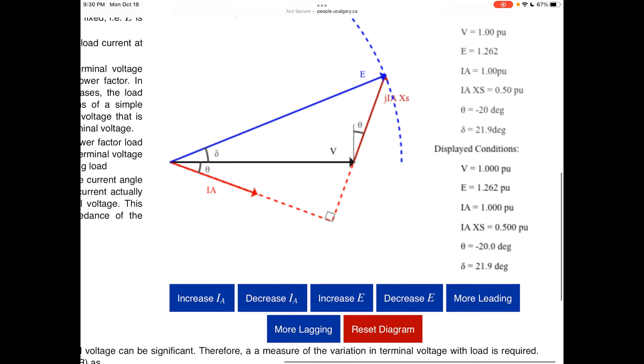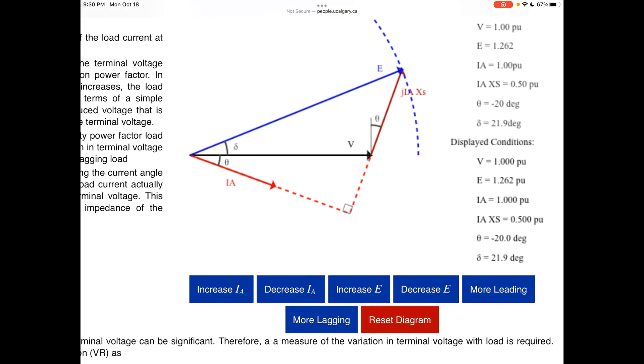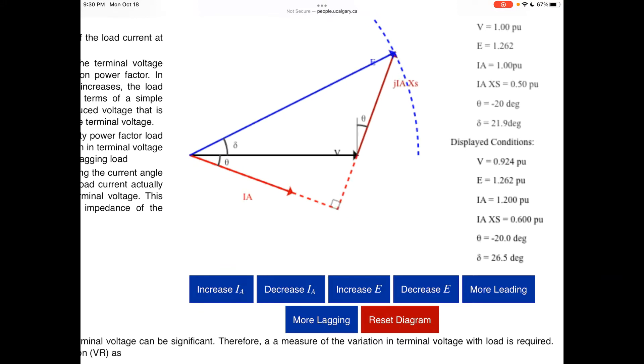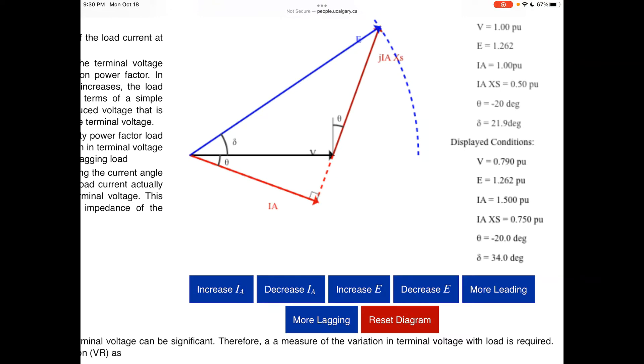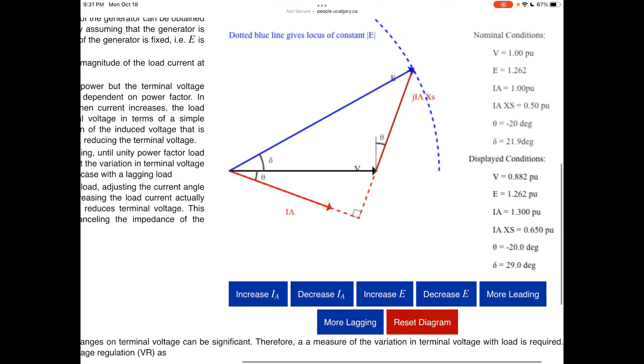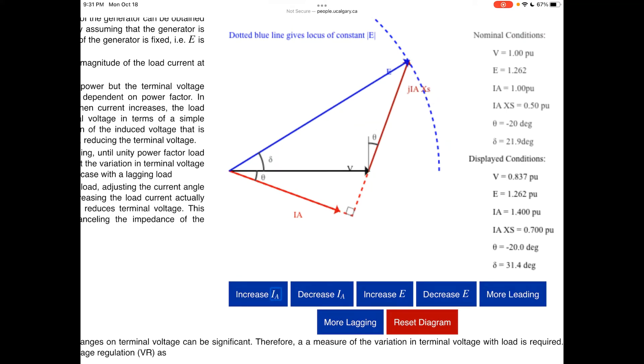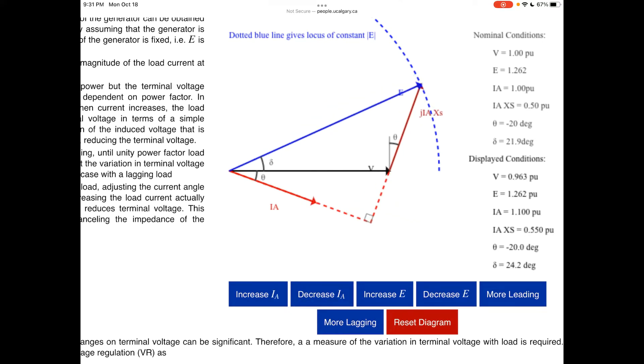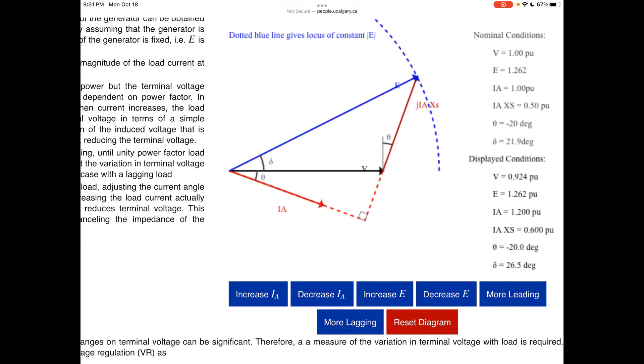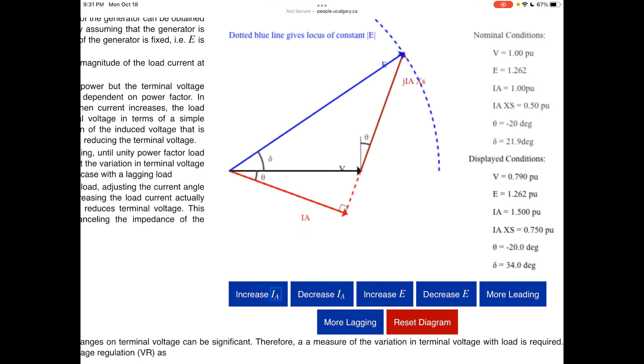If we increase E by increasing the field excitation, the terminal voltage increases with it — as expected in isolated mode where the terminal voltage is allowed to vary. The AVR controls E to restore the terminal voltage. However, increasing load also increases the power angle delta, and you cannot keep pushing it beyond the stability limit or the machine will go unstable. A more lagging load reduces the terminal voltage more, while a leading load has less impact on the terminal voltage.